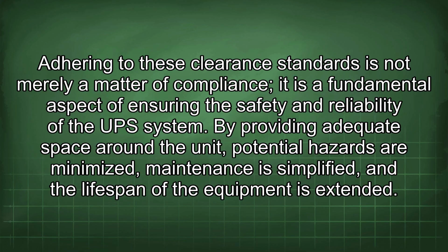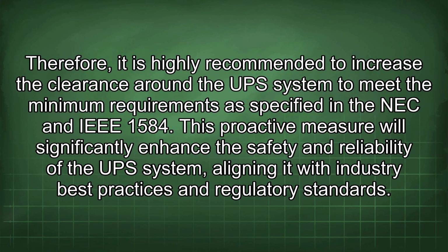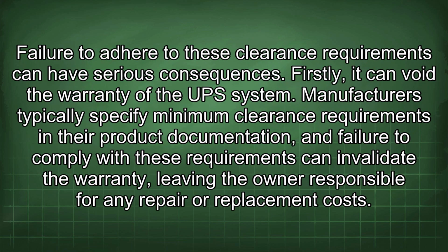By providing adequate space around the unit, potential hazards are minimized, maintenance is simplified, and the lifespan of the equipment is extended. Therefore, it is highly recommended to increase the clearance around the UPS system to meet the minimum requirements specified in the NEC and IEEE 1584. This proactive measure will significantly enhance the safety and reliability of the UPS system, aligning it with industry best practices and regulatory standards.